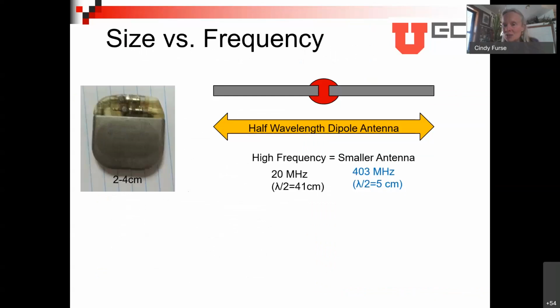And here was the challenge we were facing. The frequency that's typically used for communication is 403 megahertz. It's actually 402 to 405 megahertz. So we are designing at 403. So you can see that at high frequencies, if we were able to go to higher frequencies, we can get a smaller antenna. That's good. But we also have more loss in the body. So if you just imagined a half-wave dipole, this is how large it would have to be inside the body at those frequencies.